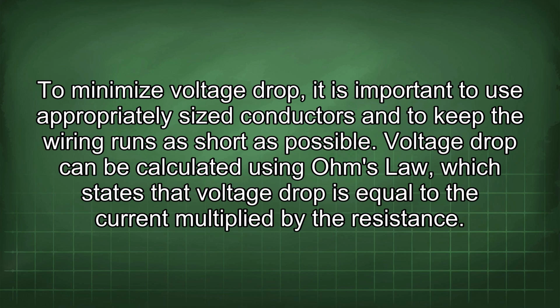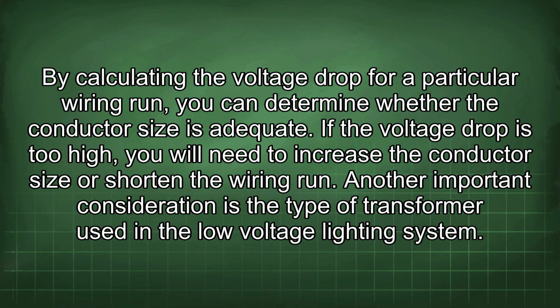as possible. Voltage drop can be calculated using Ohm's law, which states that voltage drop is equal to the current multiplied by the resistance. By calculating the voltage drop for a particular wiring run, you can determine whether the conductor size is adequate. If the voltage drop is too high, you will need to increase the conductor size or shorten the wiring run. Another important consideration is the type of transformer used in the low-voltage lighting system.